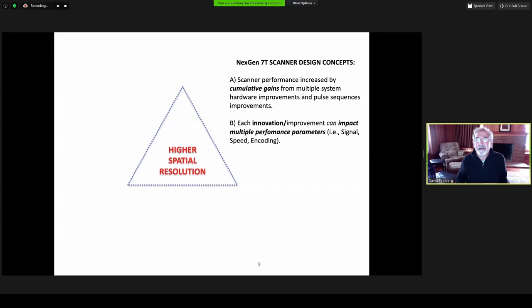I want to go over some basic design concepts. First is that the scanner performance is increased by cumulative gains from multiple different hardware improvements and pulse sequence improvements. The innovation improvements can impact multiple different performance parameters. For spatial encoding, we need more signal to support the higher resolution and also much higher acquisition speeds because we're dealing with larger data matrices and more slices.